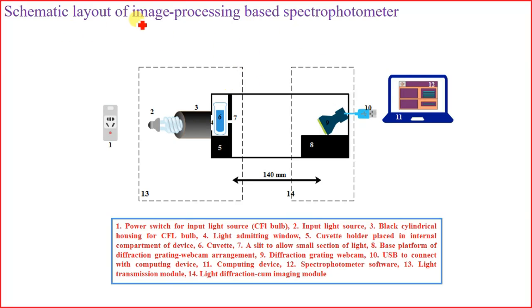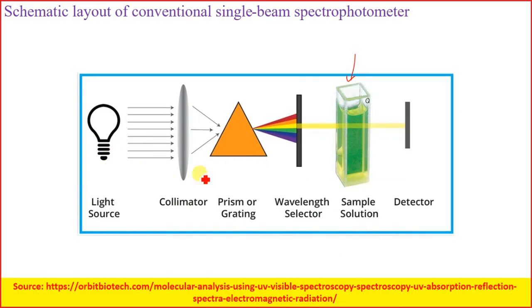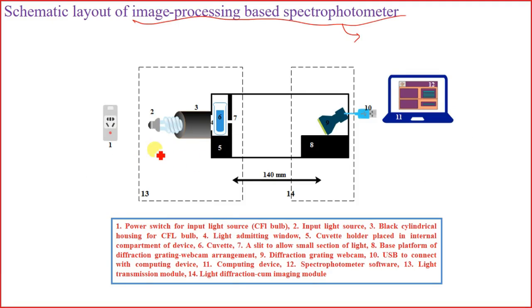When talking about an image-processing-based spectrophotometer, it is essentially a single beam spectrophotometer. The architecture has a light source, some optics, then the solution, then a detector — just like a single beam spectrophotometer. So the measurement procedure remains the same: you measure the reference spectrum first and keep it recorded in memory, then subtract it from the test measurement.